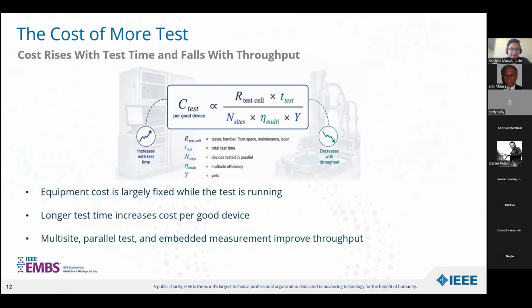We can test multiple devices at the same time, doing parallel testing of compatible devices and channels. Embedded test, the main topic of this presentation, can also reduce the amount of external instrumentation and data collection needed. But embedded test doesn't come for free—it adds circuit area, design effort, additional verification, and more power. So the goal isn't simply to add more tests, but to identify the measurement that provides additional confidence justifying that cost.